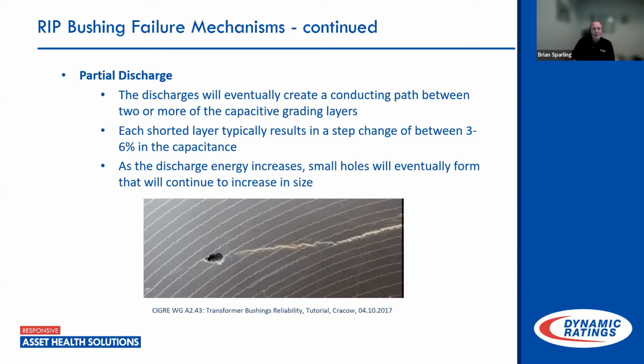But this is a failure mode of an RIP bushing. Here you can see the layers, the concentric foils that are wrapped around. This is one where discharge started, and it grew between the capacitive grading layers. So it just begins to short out the capacitive layers inside the bushing and create this discharge. Energy increases, small holes will eventually form and continue to increase in size. That is what the failure of an RIP bushing looks like.